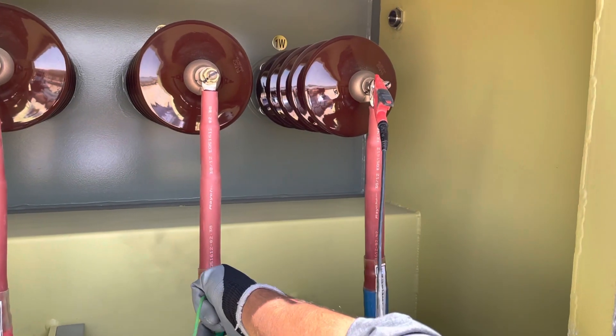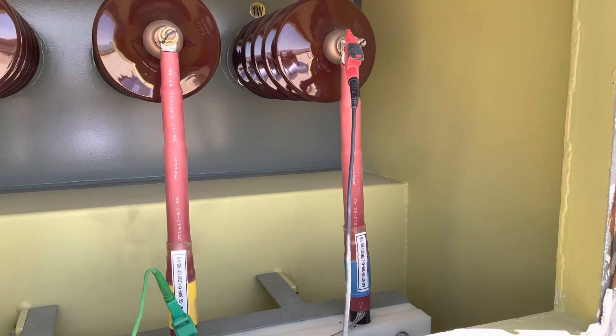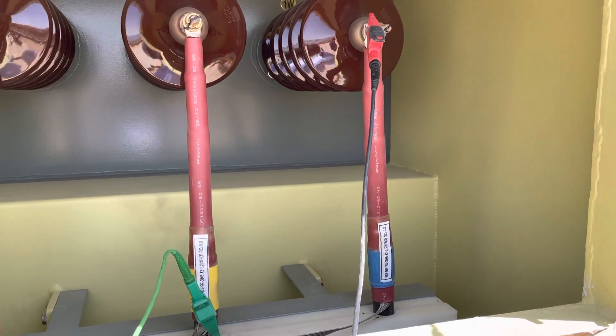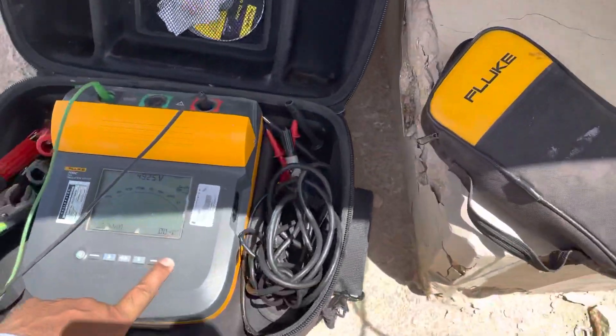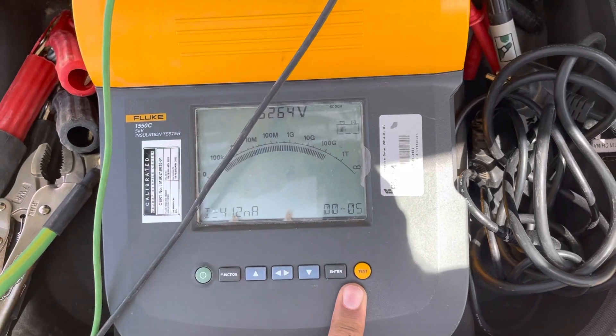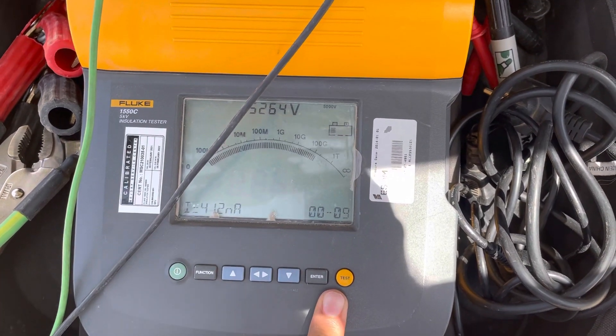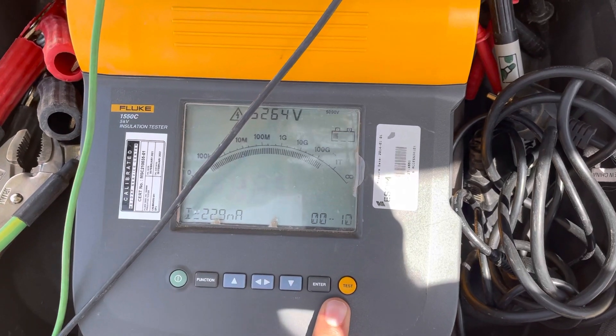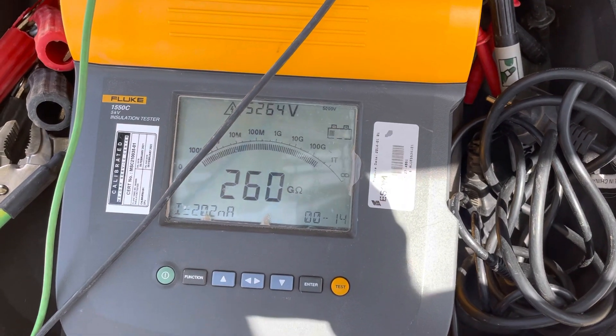We are doing one more time the megger after hipot test. The first one was the initial megger; this one is the final megger after hipot test. We'll start the megger at the rate of 5 kVDC. This will do the after-hipot megger testing for one minute.